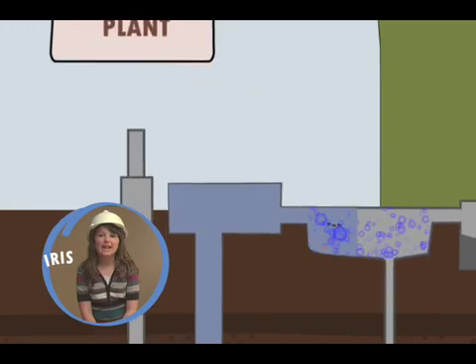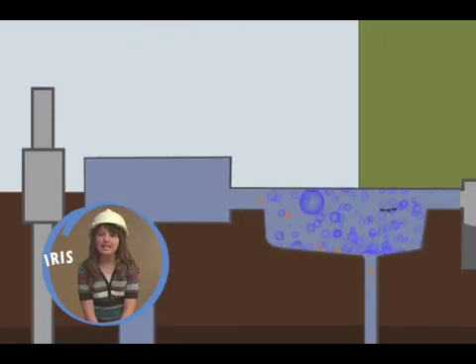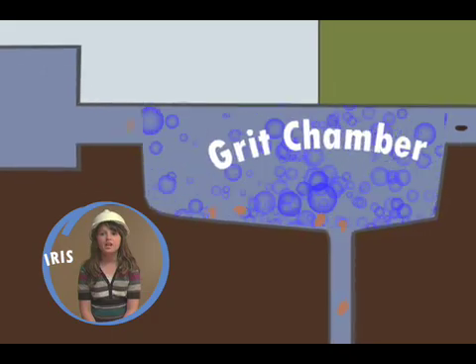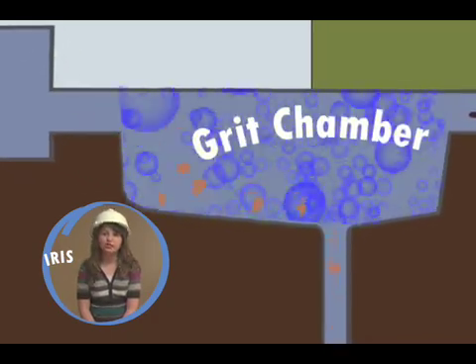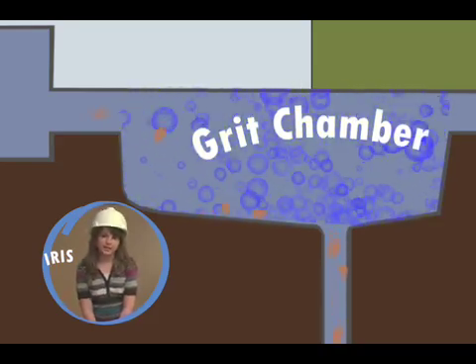The wastewater goes through an aerated grit chamber where grit material is settled and removed. This is mostly heavy inorganic grit material that was able to pass through the screens. The removed grit can go to the landfill or be cleaned and reused as a useful product such as fill material.